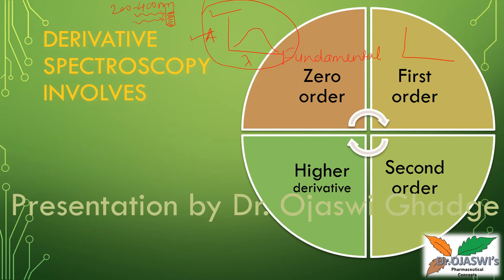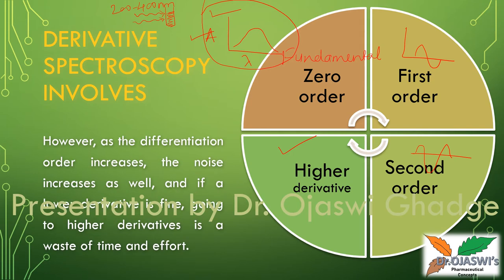We simply click on the software to convert the fundamental spectrum into first-order, then second-order, and higher derivatives such as third and fourth order. However, as the differentiation order increases, the noise also increases. If a lower derivative is sufficient, going to a higher derivative is a waste of time and effort.